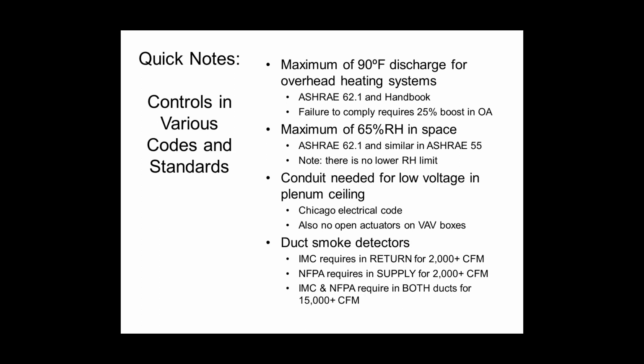Duct smoke detectors typically fall under the controls guys a lot. Sometimes the mechanical provides them, sometimes the controls provides them, sometimes the fire protection contractor provides them, but somebody's got to provide them. The International Mechanical Code requires duct smoke detectors in the return duct whenever it is a 2,000 CFM or larger system. NFPA requires it on the supply duct whenever it's 2,000 CFM or larger. If you are in a jurisdiction that is following both NFPA and IMC, then guess what? You've got to put one in the supply and in the return. You've got to do both.